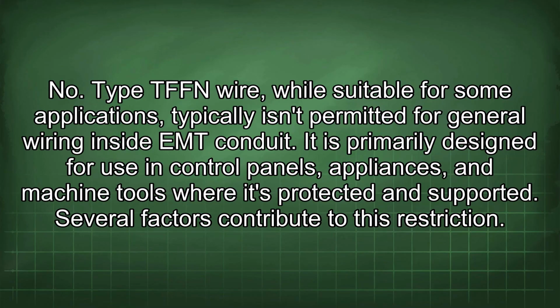Type TFFN wire, while suitable for some applications, typically isn't permitted for general wiring inside EMT conduit. It is primarily designed for use in control panels, appliances, and machine tools where it's protected and supported. Several factors contribute to this restriction.